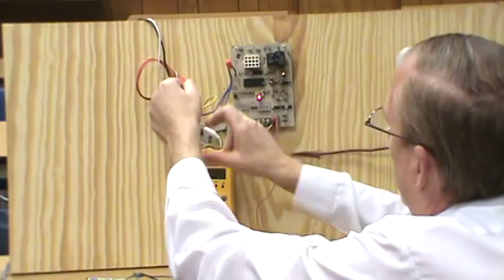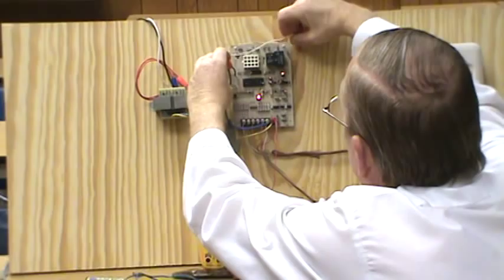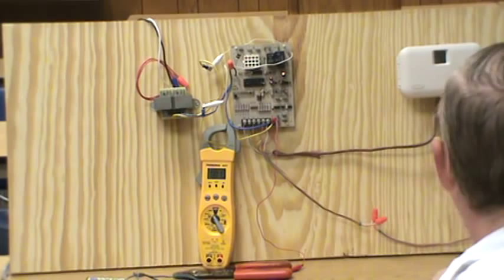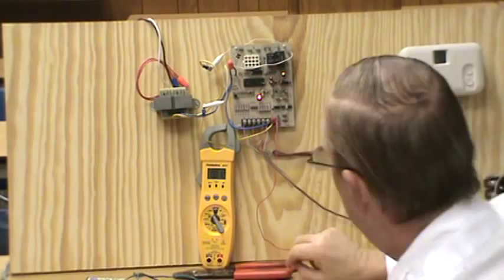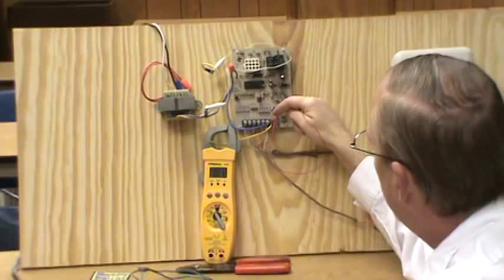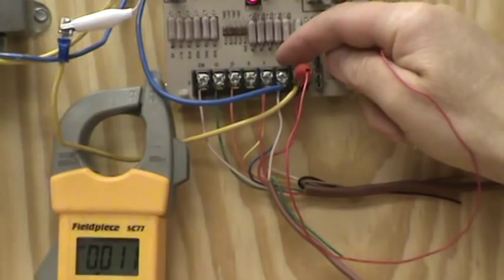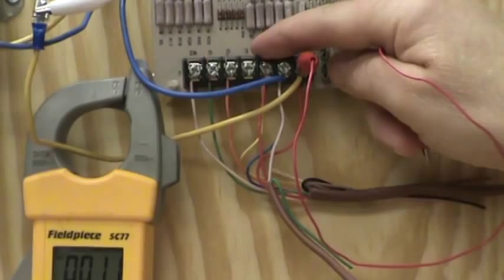And right now I'm going to try to demonstrate like if we had a short. I'm going to put it across the cooling circuit, across the coil of this contactor we have off to the right over here. I'll just create a short. And with the jumper lead, what we have over here is our red load side from the secondary of the transformer. The second terminal is common ground, and the third is going to be your cooling circuit. This is the one I'm going to short out.